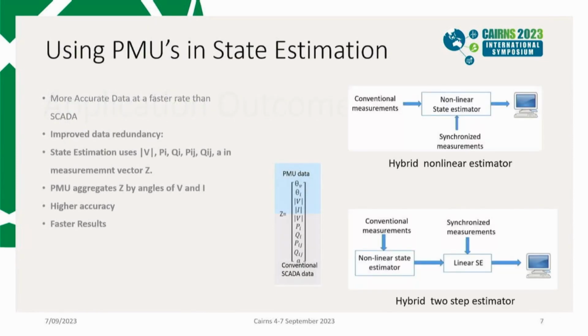So firstly, state estimation today is an important part of managing a distribution network, and the PMU data that we gathered allowed us to provide really state measurement as opposed to state estimation. So by gathering the phasor information at the different points on the distribution grid, you can calculate your impedance values all over the network, and that gives you higher performance for your network state estimation, and also gives faster results because it relies on less computation. It's more relying on additional empirical data that you gather. And so we can see an improvement in the quality of the state estimation of the distribution grid.